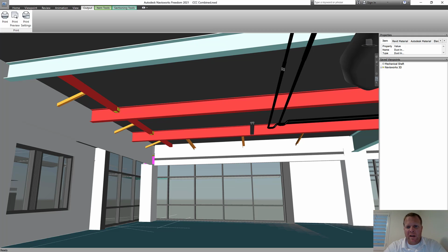But I really like having this pipe under pressure during construction. So if we get to a point where this is completed and they do a pressure test on it, I usually ask them to leave the pressure test on. What that indicates is that somebody hit it, with a scissor lift or something like that.